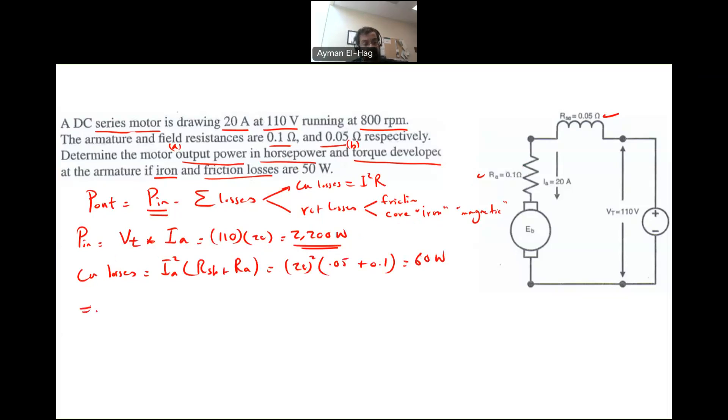So then your P out will equal to P in, which is 2,200, minus the copper loss, which is 60, minus the rotational loss, which is 50, and this will give us 2,090 watt, which is equal to 2,090 divided by 746 to convert from watt to horsepower, and this is approximately 2.8 horsepower. So this is the first requirement.